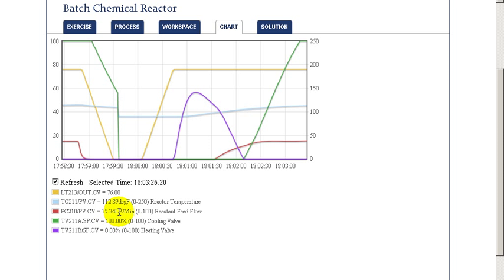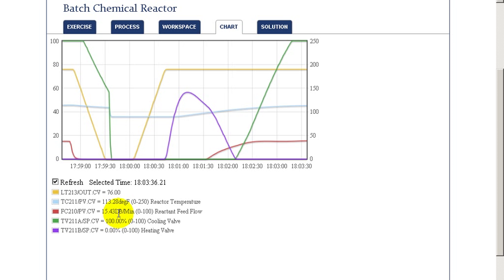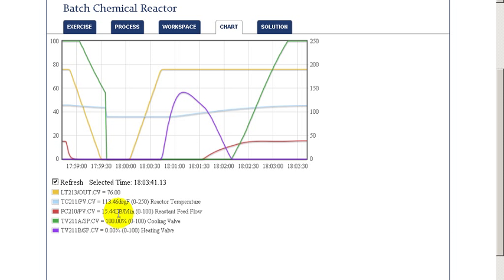And what we see is that we're not able to achieve the target of 20. The temperature override has kicked in and has limited the amount of flow to keep the temperature from exceeding the override set point.